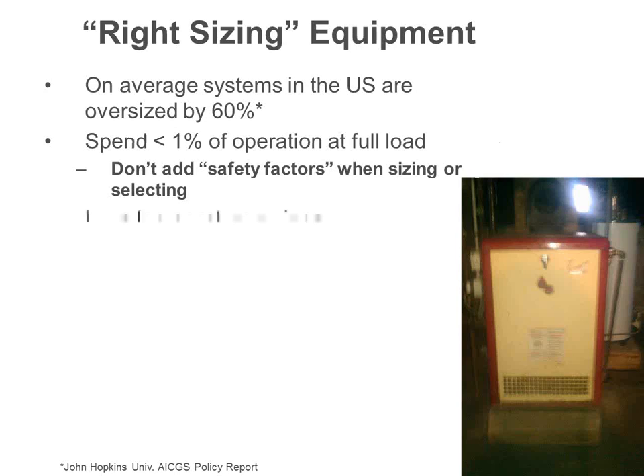Radiation method. This is basically, you can only put so much stuff in a 12-pound bag. Okay? So what we're doing here is, it's not as accurate as a load calc, but can be done with a lot less input data. It's also pretty easy. This requires no more than a tape measure and basically a lighted mirror or whatever to double check the baseboard. There's less oversizing than simply reading the old tag, and like we said, you can only put 12 pounds of you-know-what in a 12-pound bag. You can't put more BTUs into a system when it doesn't have that amount of radiation available.